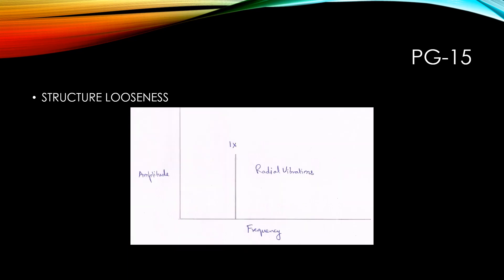Now the case of structural looseness. This type of looseness is caused by structural looseness or weakness in the machine feet, base plate, or foundation. It can also be caused by deteriorated grouting, loose hold down bolts at the base, and the deterioration of the base frame or base, known as soft foot.